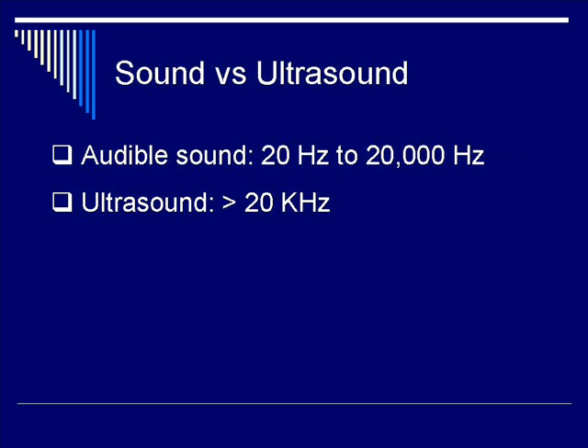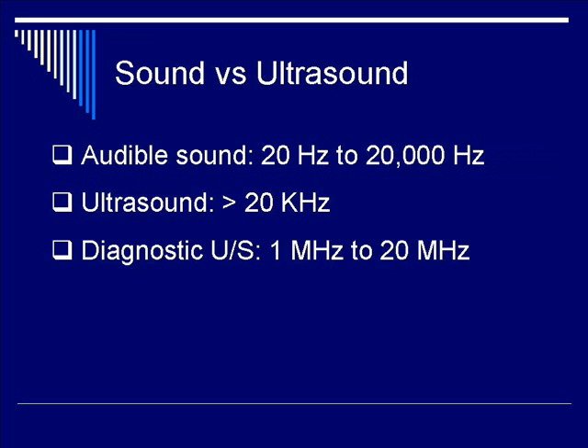Therefore, unless we have characteristics of a bat, we typically do not detect ultrasound. However, during the Doppler measurement employed during a vascular study, for example, oftentimes we can hear audible sounds because the Doppler frequency falls within the audible range. Diagnostic ultrasound consists of probes that have frequencies ranging from 1 MHz all the way up to 20 MHz. Abdominal probes typically have a lower frequency range, whereas vascular probes can be upwards of over 10 MHz or more.